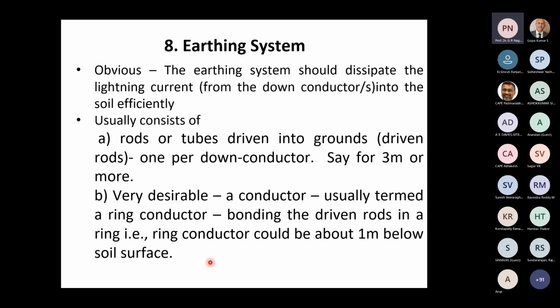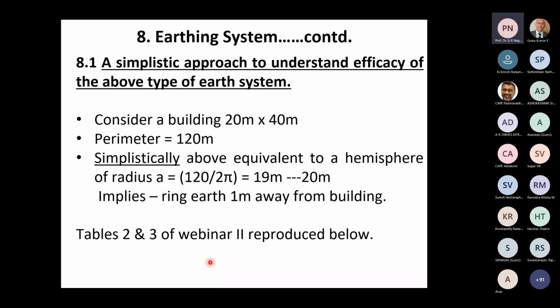The function of this is very obvious. The current distributes all along this ring, and therefore the current density when it enters the ground is comparatively very small. Now, to see a simple example, consider a building of 20 meters by 40 meters. The perimeter is (20 plus 40) into 2, that is 120 meters. Simplistically, this is equivalent to a hemisphere of radius a, that is 120 divided by 2 pi, approximately 19 to 20 meters. So it's equivalent to a hemisphere of radius 20 meters.